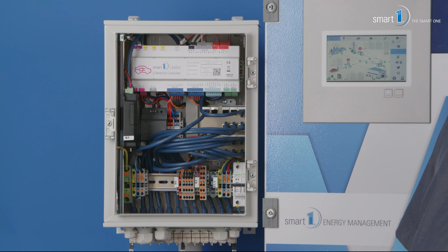And the next thing that we do is we connect the DSO signals to the system. For the DSO signals, we have down here the ports to connect the DSO signals. So we have digital functionalities. We also have an extension module if you require analog connections, but we also have something that we call the IEC protocol port. And you can see that also here, these are the RS485 ports where you can directly connect your DSO interface, like with IEC 101 or 104 through Ethernet. You can also have a direct communication to the grid operator. So everything is inside this box, everything is wired now into the system. If you want, you can also add a PV and a battery as an add-on to the system.